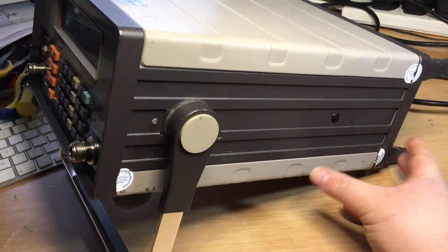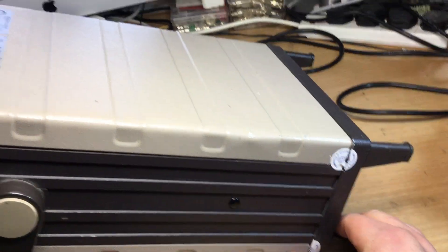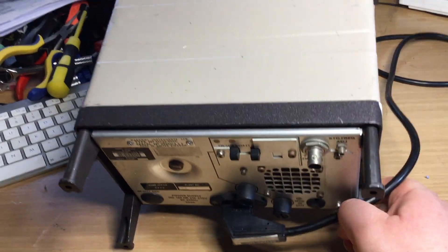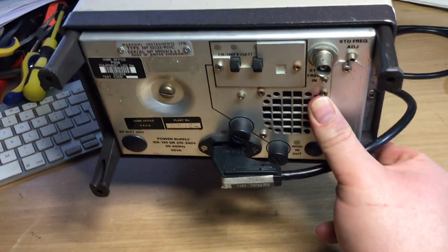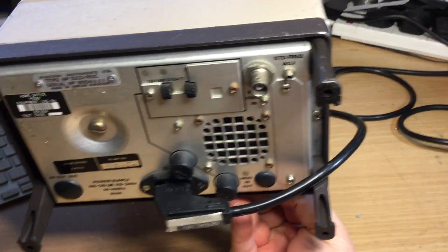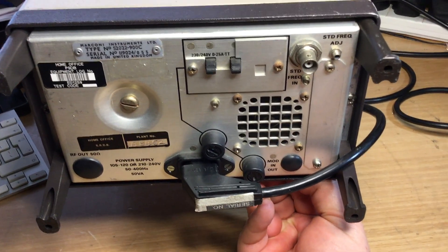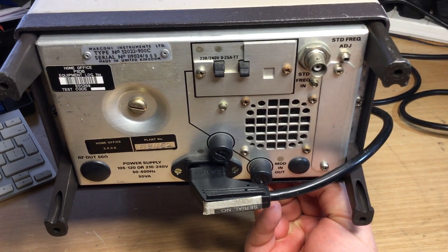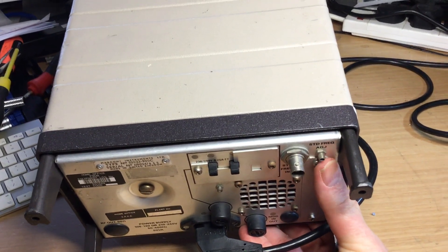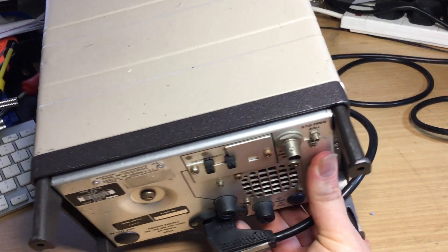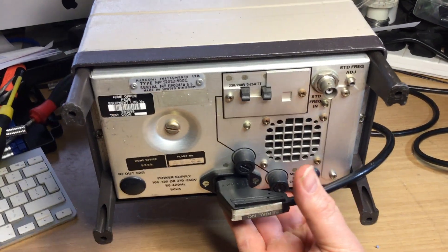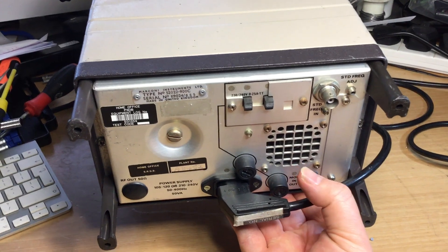On the rear we've got voltage selection for different countries' power supplies, and we have a frequency standard input on the top right. We can also calibrate it as well using this adjustment pot there to adjust it, and we can select different voltages and the fuses at the back.